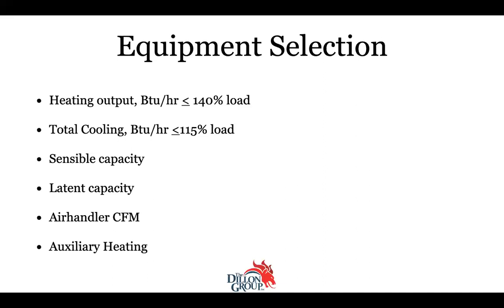I can't tell you the number of times they don't tell me at all what kind of heat strip they put in for auxiliary heating on heat pumps. What size is it? It's never marked. I'm like, how am I supposed to know? I'm supposed to verify that this system conforms. So we have to chase the HVAC guy down and he goes, oh, I always put in 8 kW. Or I always put in 5 kW. One guy said, I always put in two banks of 10s. I'm like, well, what did the load call for? There's actually some math you can do, some science about this.